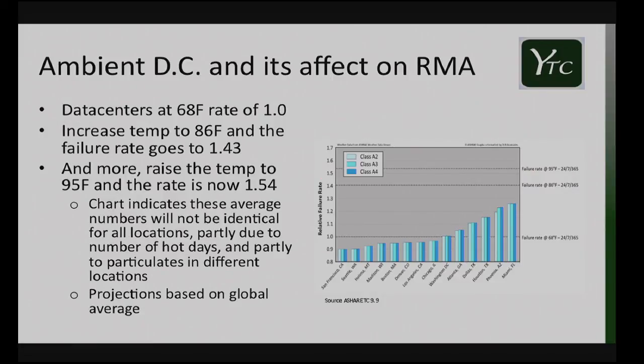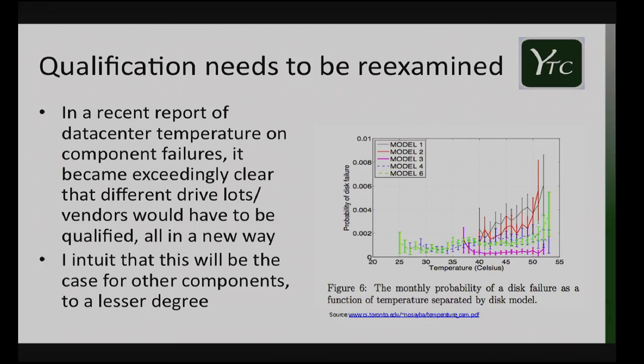As we get into the ambient data center, failure rates are going to go up. If you've been in a cold data center, you'd be at the 1.0. If you get into a data center that's at 95, you should expect basically 54% higher failure rates. Those failure rates are not going to be uniform across the world, depending on how you do all this work, et cetera. But qualification needs to be re-examined. How you do your qualifications is important.